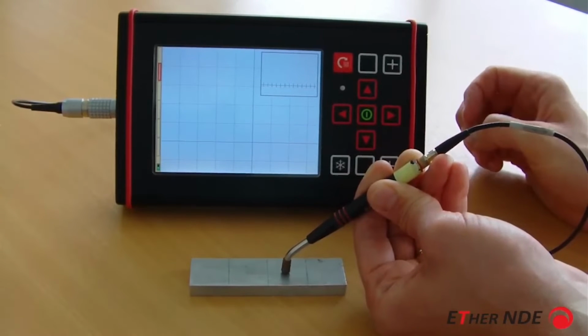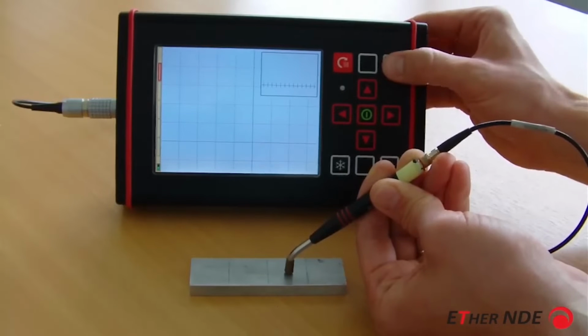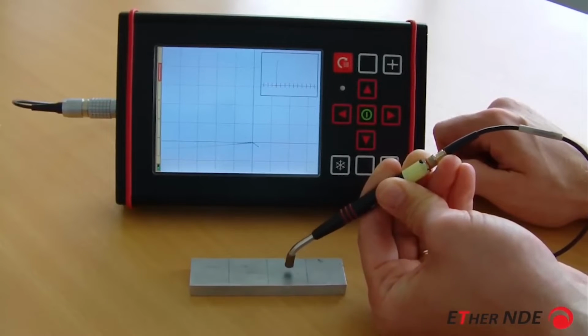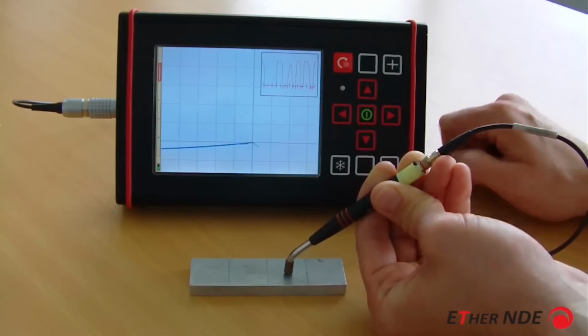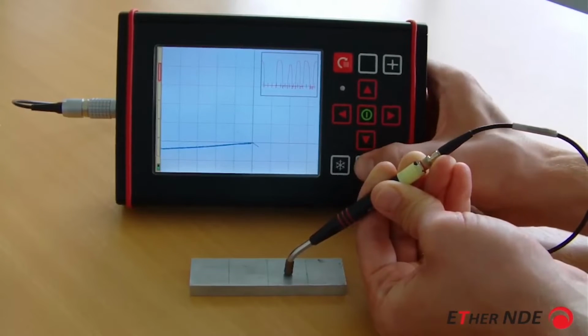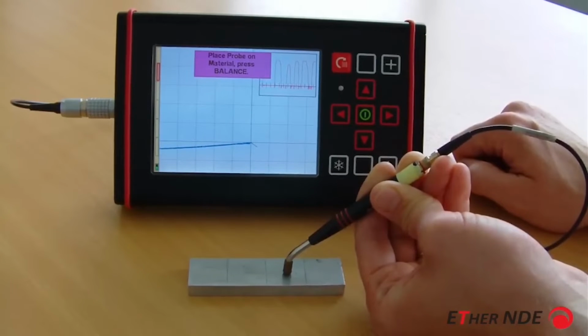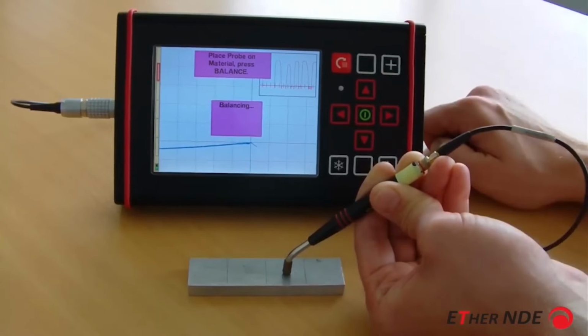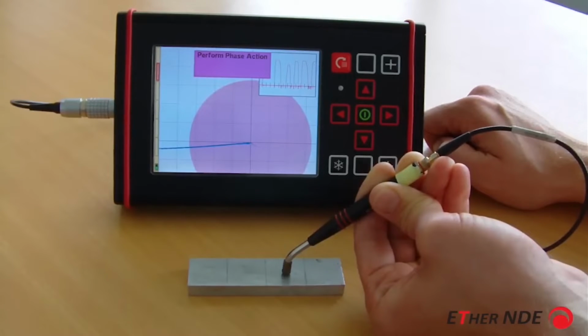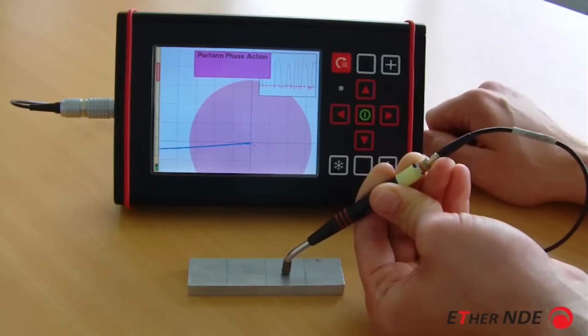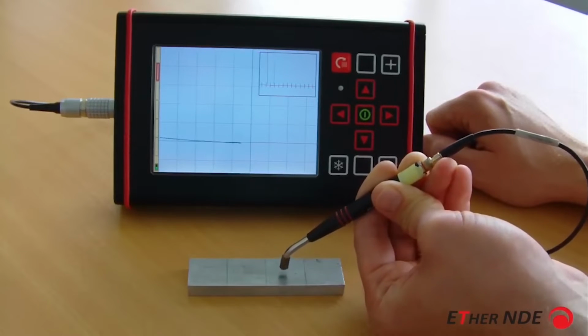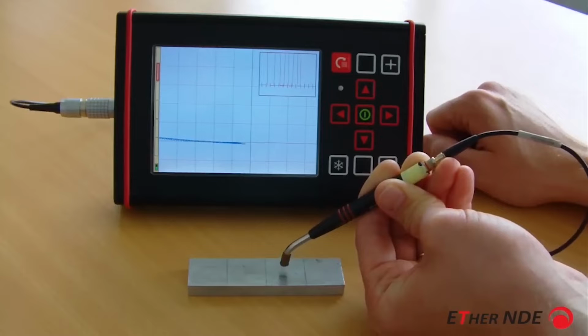So the next step is to set lift off. So we do a balance. Lift off is nearly horizontal. We can slightly improve that using the auto phase. So if I place the probe on the material and press balance, now you can see we have a large circle. When the probe signal exits the circle, at that point that's rotated to 0 degrees or horizontal. There we go. So now lift off is much closer to the horizontal.